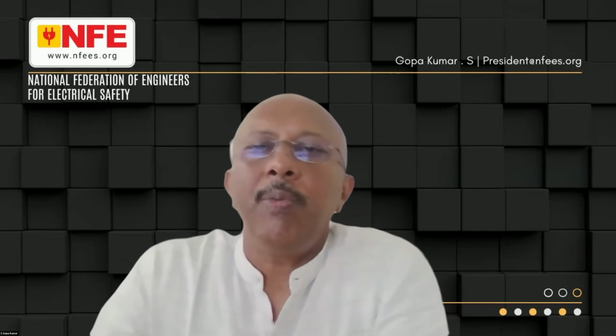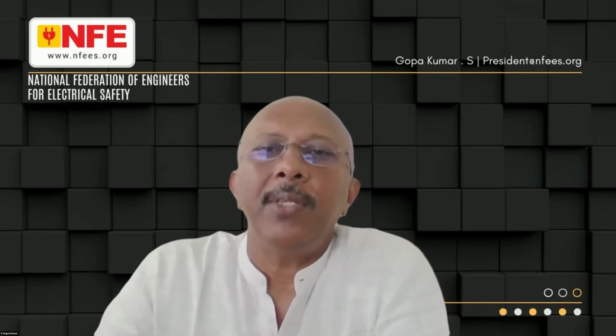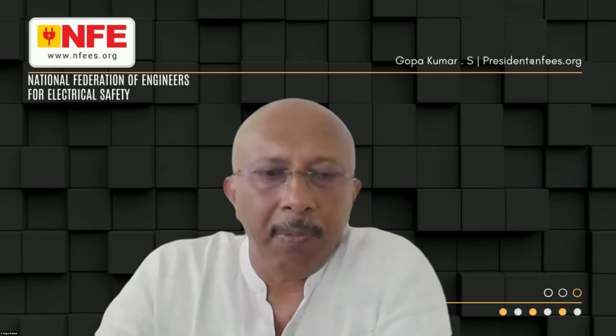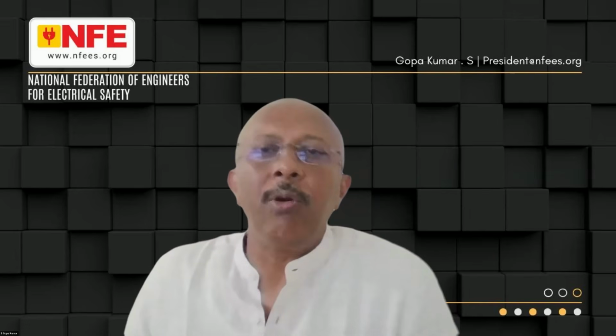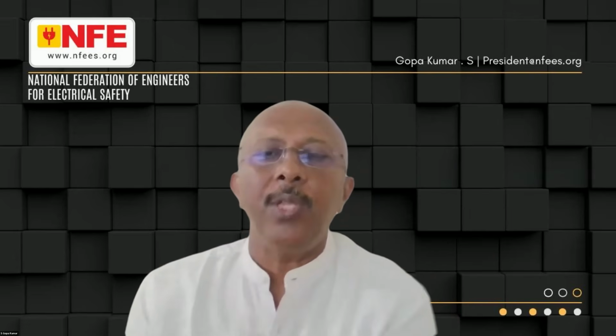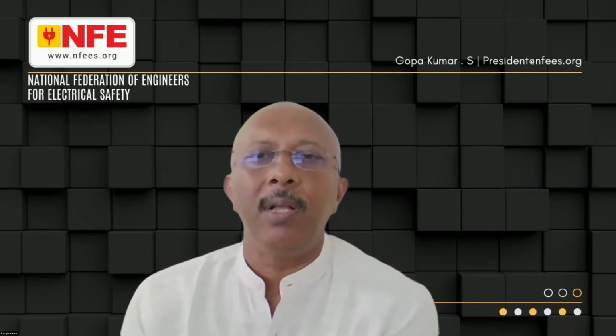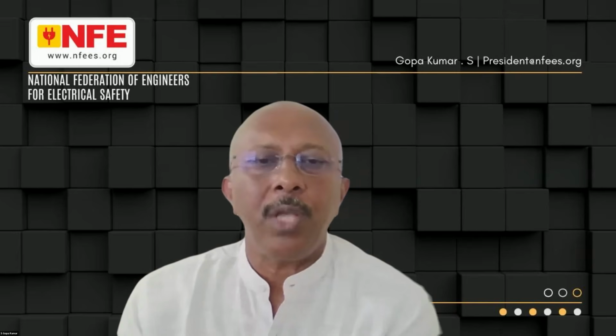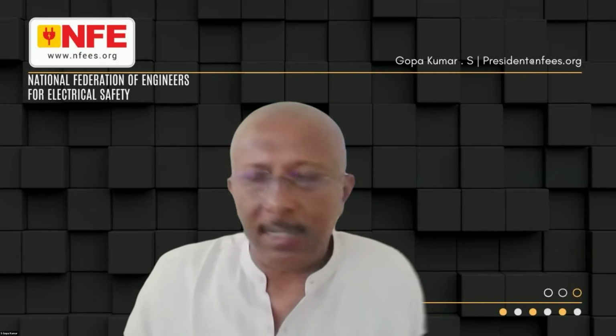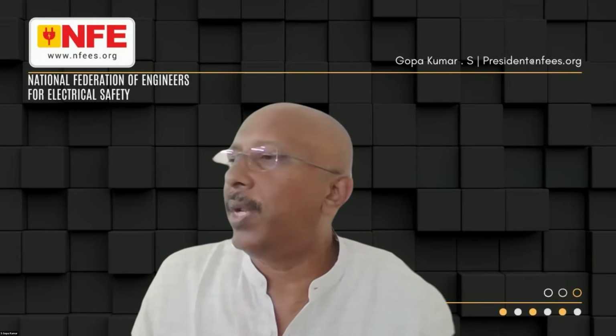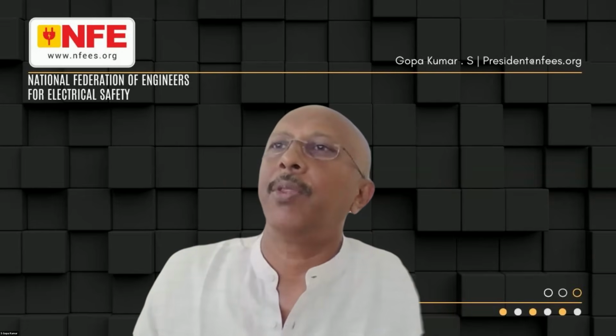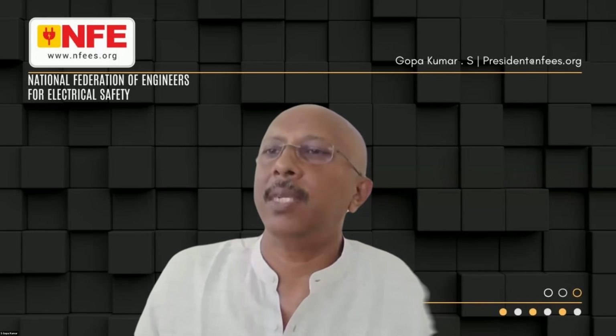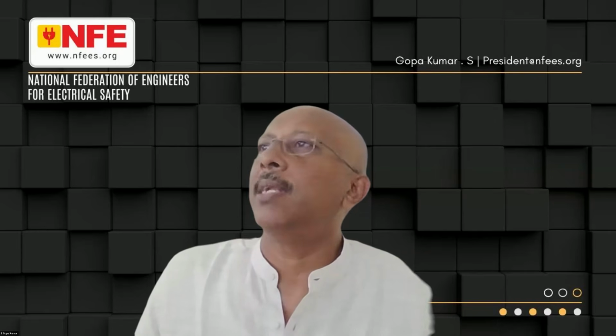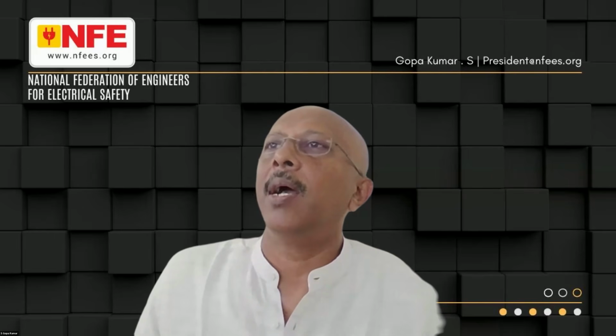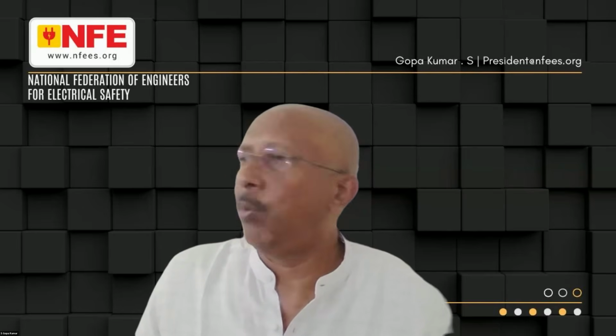Shafiq Ahmad asks, how to measure earth pit current carrying capacity? Mr. Shafiq, please note that you are not going to inject current into the earth through the earth pit. That concept is wrong. The earth electrodes are used as a system reference. Now let me show you one interesting point from the IS 3043 standard. You have to wait for a while. Let me open IS 3043:2018. I am opening. Let me share it.